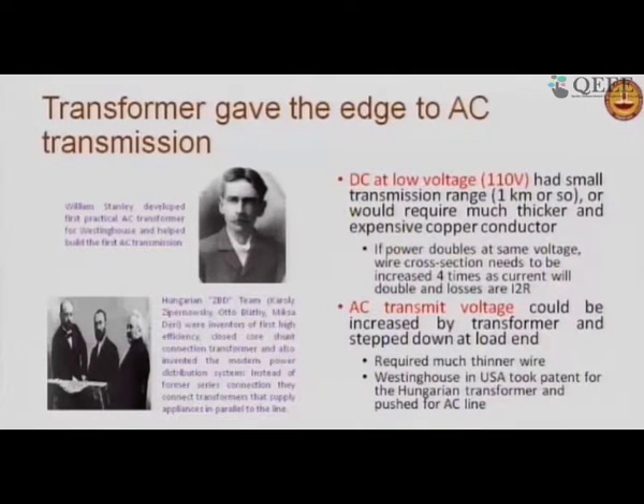Now, AC transmission voltage could easily be increased by a transformer, stepped up and stepped down. So you can start with 110 volt AC, and go up to 200 volt AC or 400 volt AC by just using a transformer. And if you go to a higher voltage like 400 volt, you will require 1/16 of the wire to carry the same current, because of I square R. Or you can go maybe 4 times the distance and still have 1/4 the thickness of wire. That will reduce the cost.